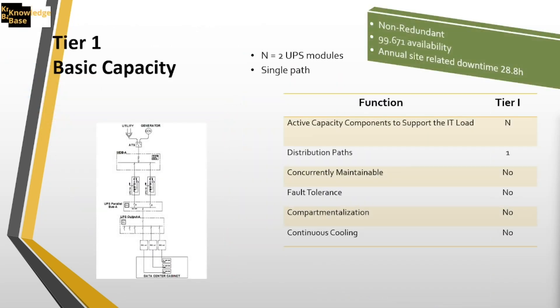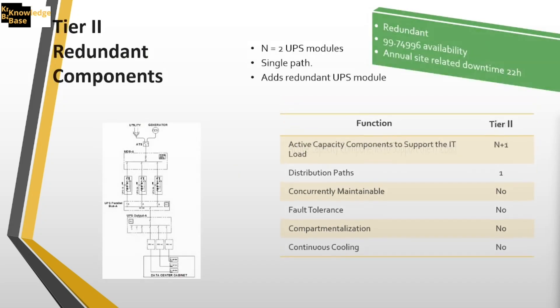Let's look at an electrical system example. In tier 1, it's a non-redundant system — we have N, which is two UPS modules. If N is 100 kW, each module is 50 kW. There is no redundancy — we have only the need, which is two UPSs. That's tier 1. In tier 2, we have N+1 redundancy: three UPSs where two are the need and one is for redundancy. If any UPS fails, power automatically moves to the standby UPS, and there's no interruption to data center operations.